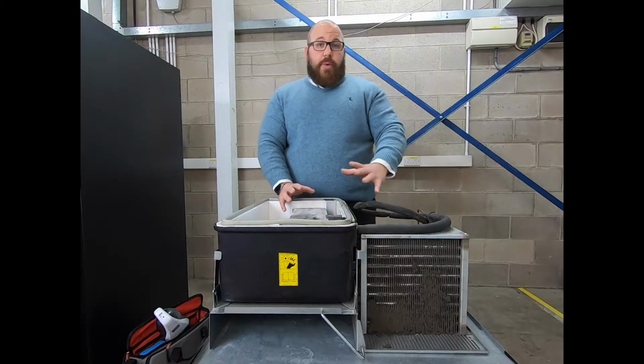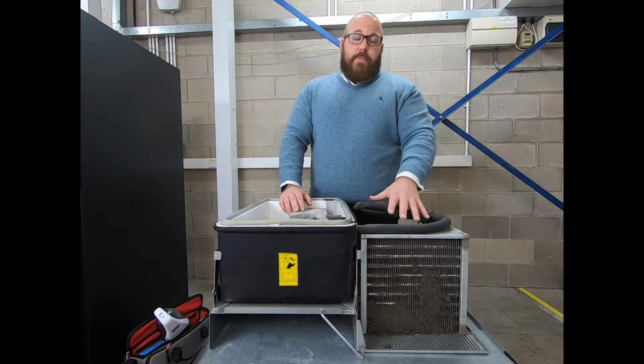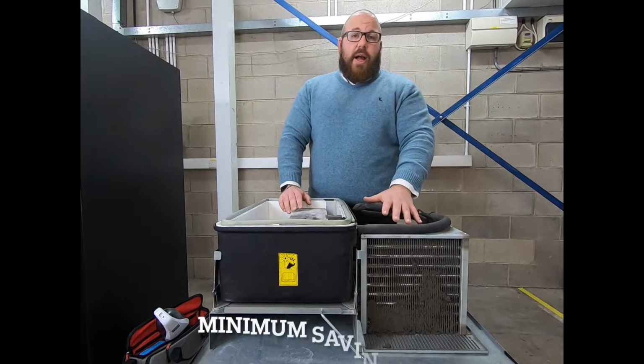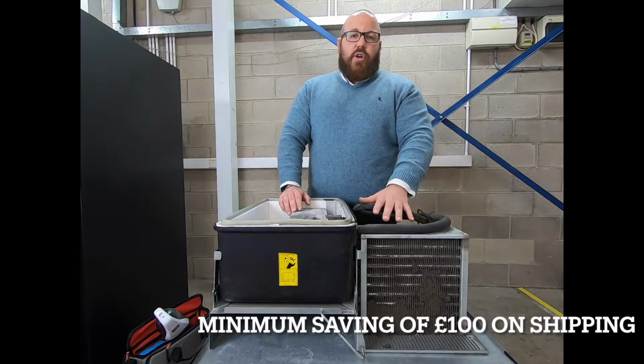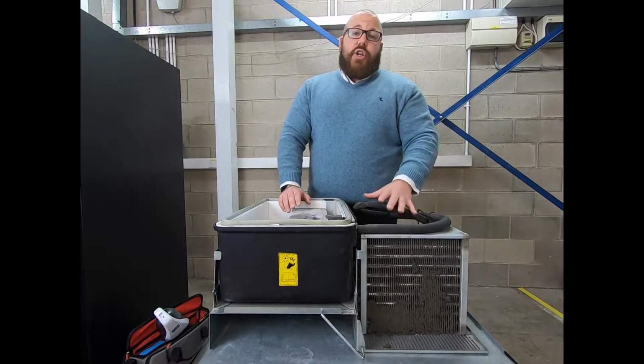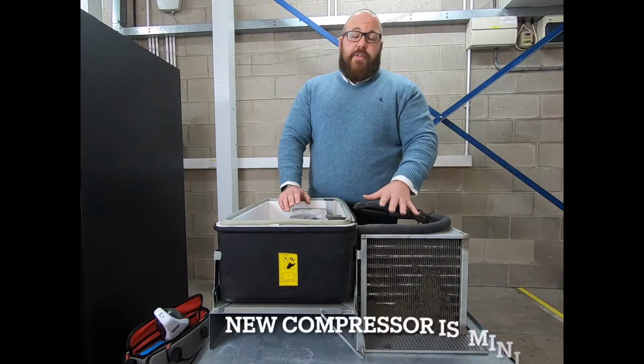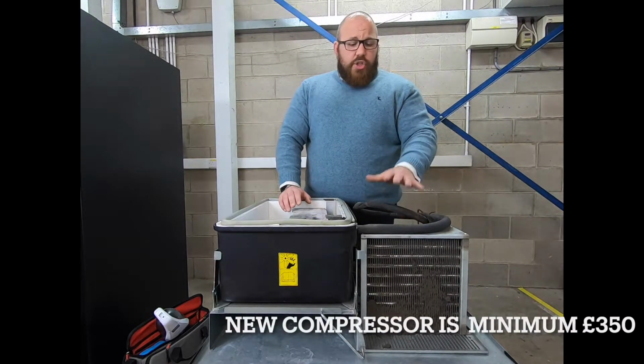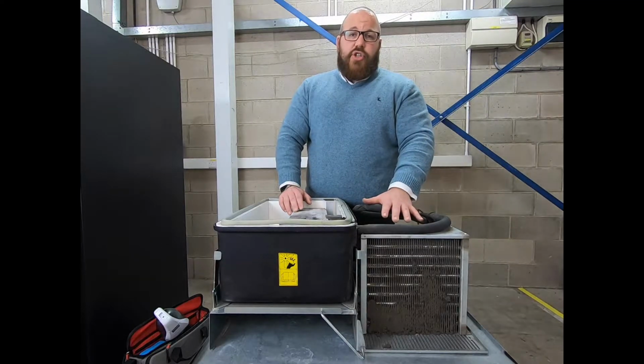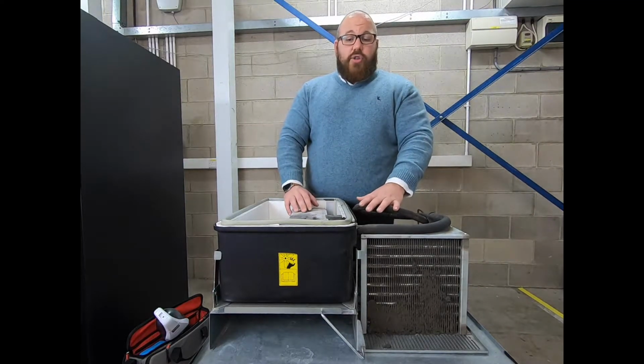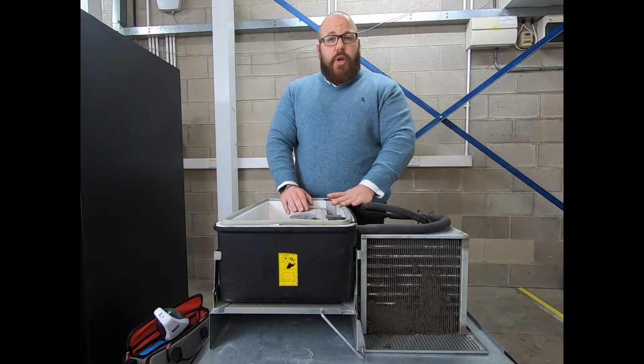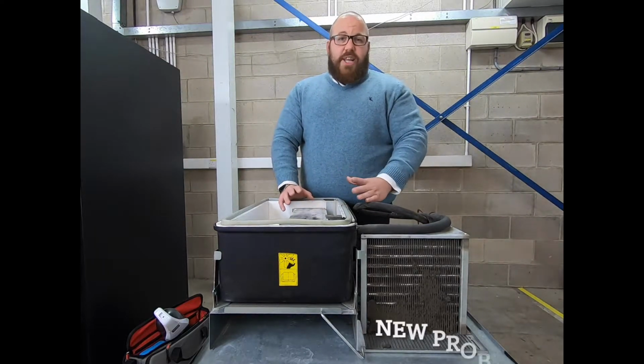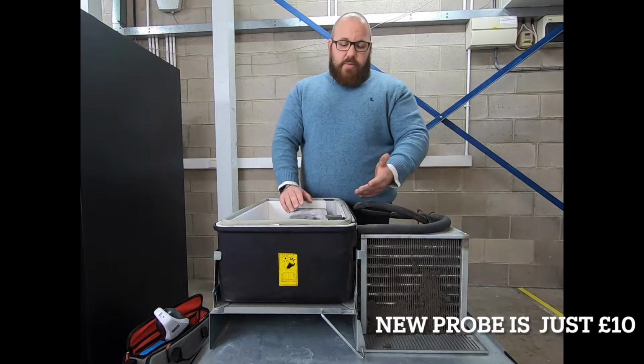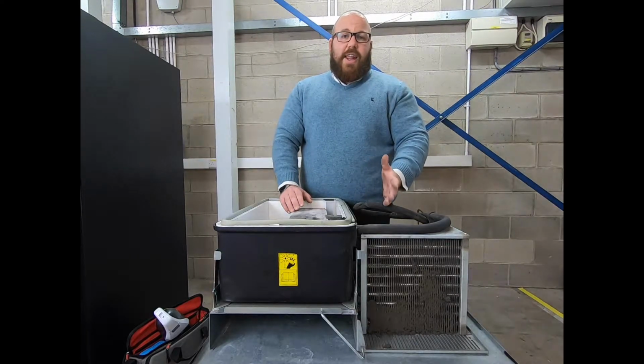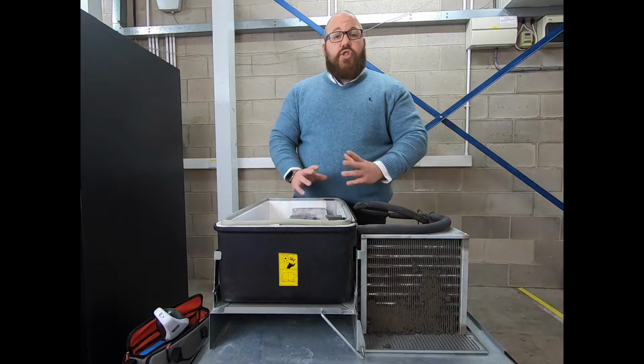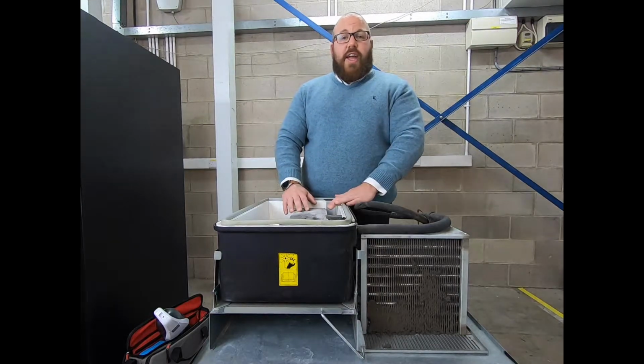Looking at the cost implications, just to ship it back and out and back costs around £100, and changing a compressor is going to cost around £350 to £400. Simply keeping it clean and running efficiently will prolong its life and save you that cost. If it's a probe issue, you can buy a new probe for around £10, which stops you having to go through the shipping process just for a part you could have changed in the field. We'll talk about how to test that and what to look at next when we move over to the machine.